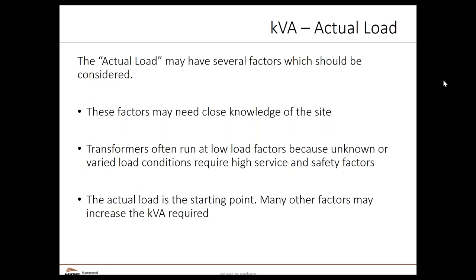Actual load is basically the load required by your end appliance or equipment. But the actual load is just a starting point — there are a lot of other factors that may increase the kVA required. That's why it's very important to have close knowledge of the site. For example, transformers often run at a low load factor because of unknown load conditions, which require higher safety or service factors.